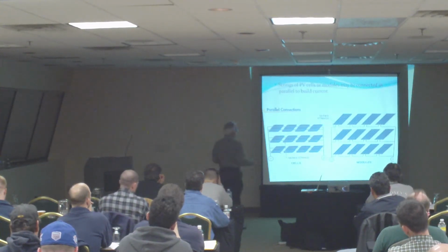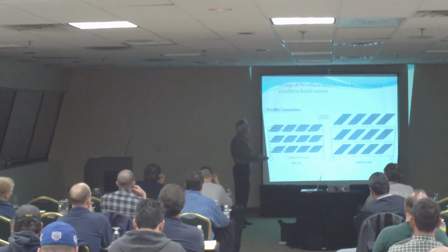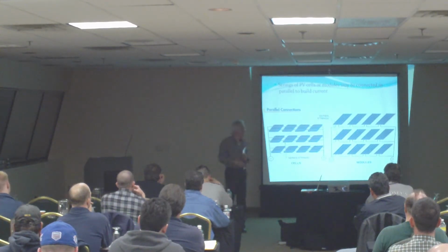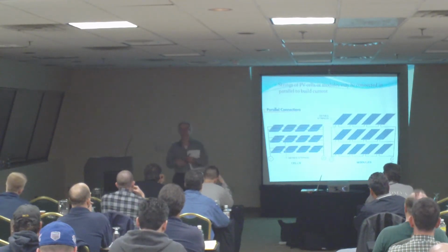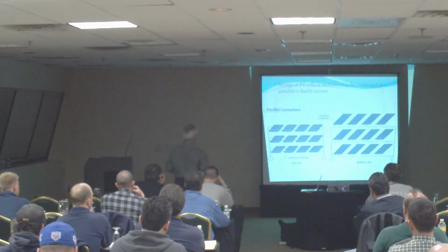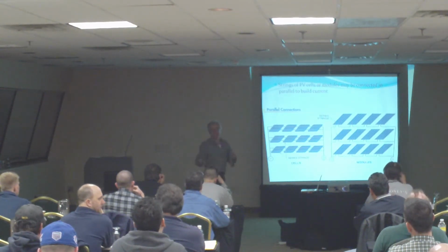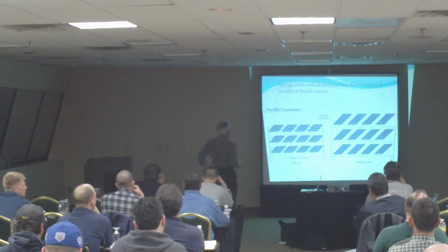I can also measure the voltages across in here to make sure that I have the voltage. But supposedly this string in here is bad, and I put my voltmeter across in here and here. What do I measure? Do I have a determination of which string is bad? No, because the voltage across any point in here would be the same, it would be the open circuit voltage. So I really need to do a couple of things.